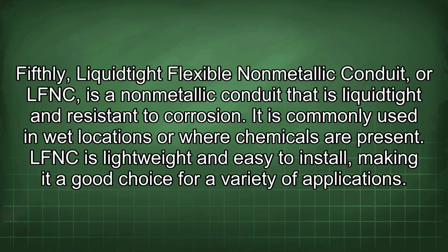Fifthly, liquidtight flexible non-metallic conduit, or LFNC, is a non-metallic conduit that is liquid-tight and resistant to corrosion. It is commonly used in wet locations or where chemicals are present. LFNC is lightweight and easy to install, making it a good choice for a variety of applications.